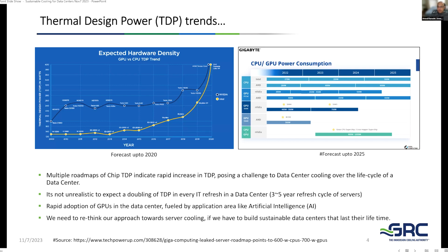A data center owner plans a data center infrastructure for 10 to 15 years in terms of a capex. So very easily, if you assume a 3 to 5 year life cycle of an IT equipment, at least 3 refreshes are given in a data center infrastructure which you are planning right now. And looking at these charts, it is very easy. Every IT refresh will practically double the power consumption of the CPU. And so customers have started wondering, what kind of a data center should I design today so that it is able to take 2 and 3 more refreshes of IT? And that is where air cooling is becoming a challenge.